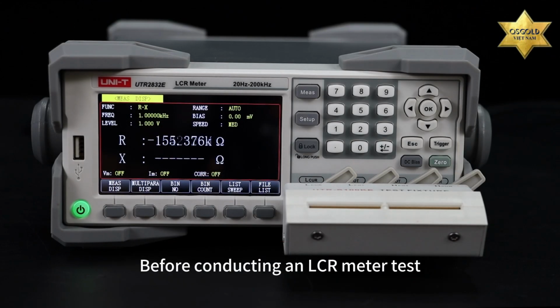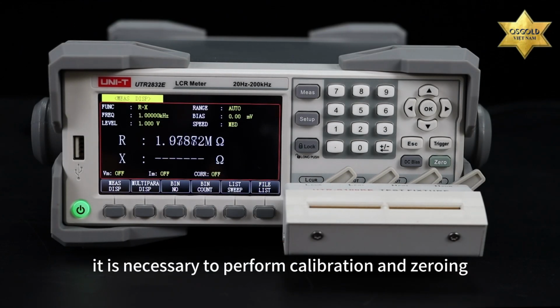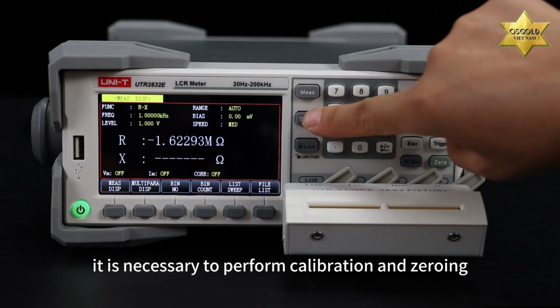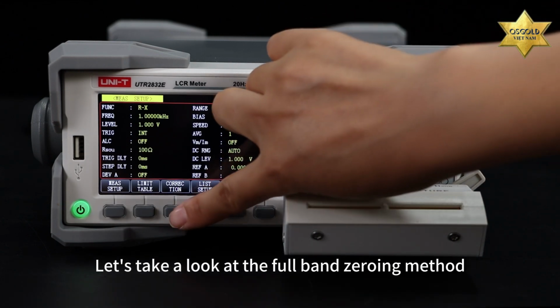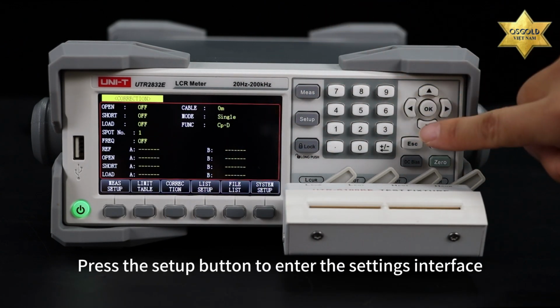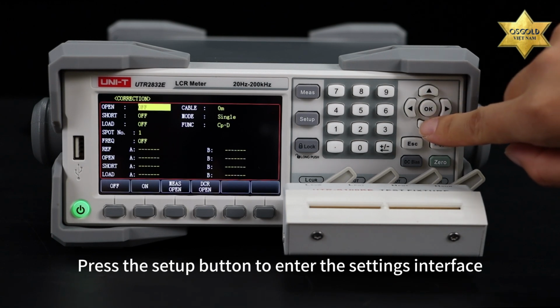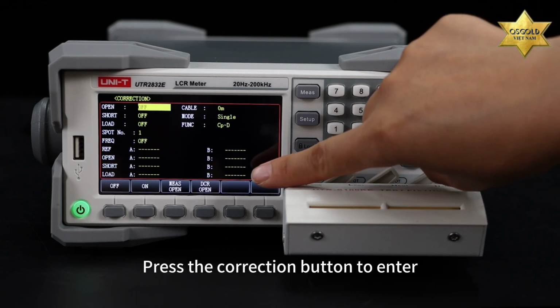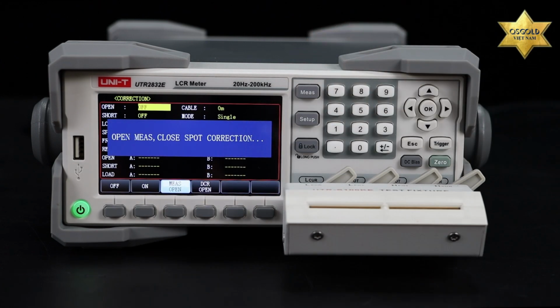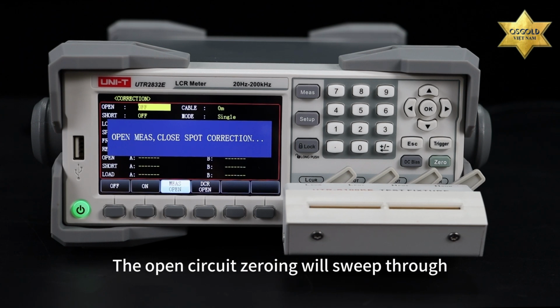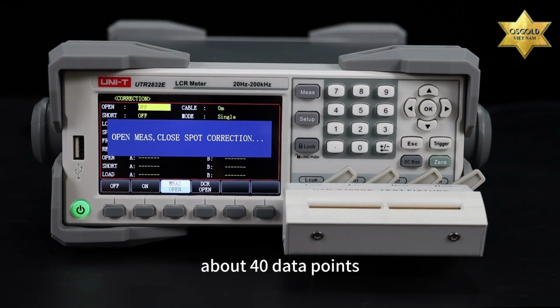Before conducting an LCR meter test, it is necessary to perform calibration and zeroing. Let's take a look at the full band zeroing method. Press the Setup button to enter the settings interface. Press the Correction button to enter the calibration interface. With the test end open-circuited, perform an open circuit zeroing. The open circuit zeroing will sweep through about 40 data points. The zeroing process is relatively slow.